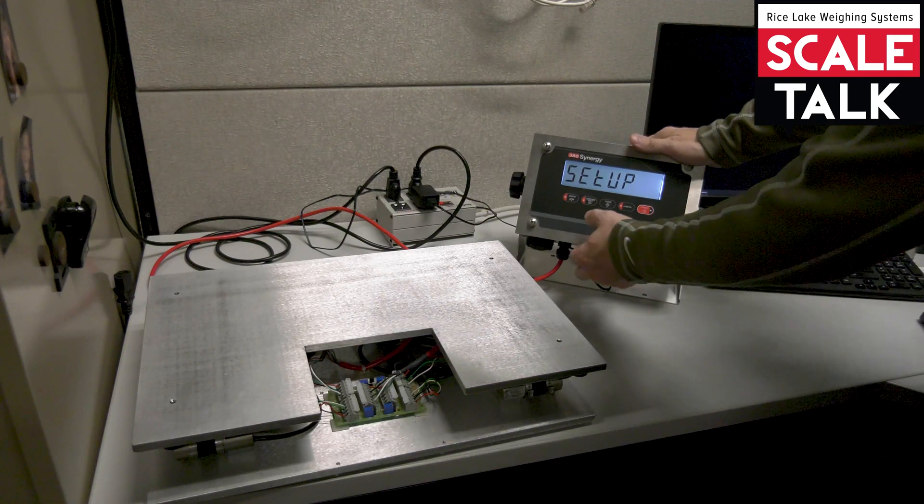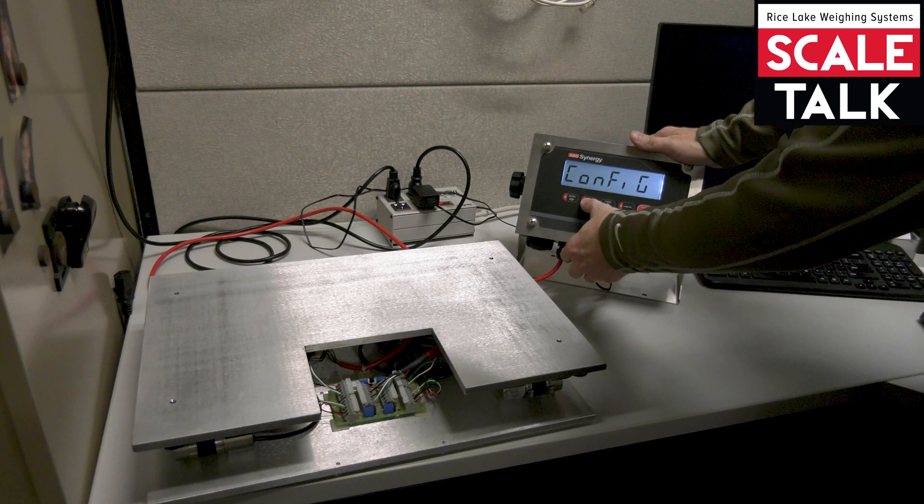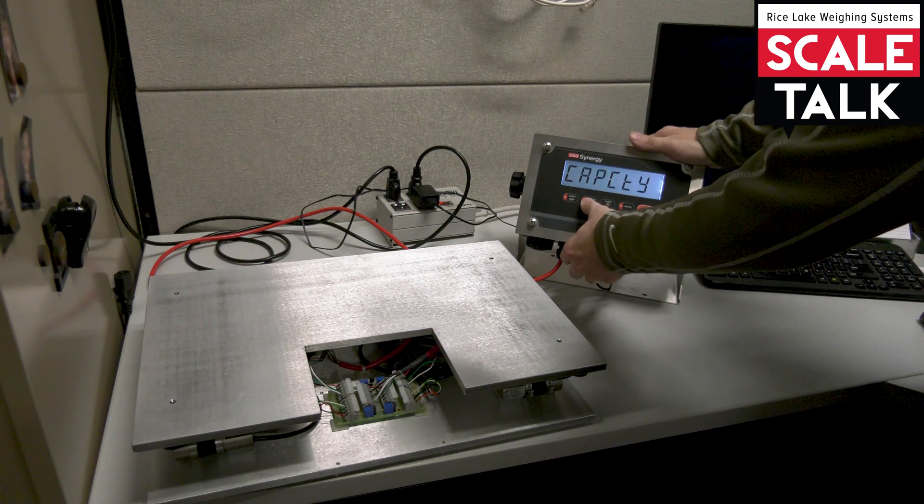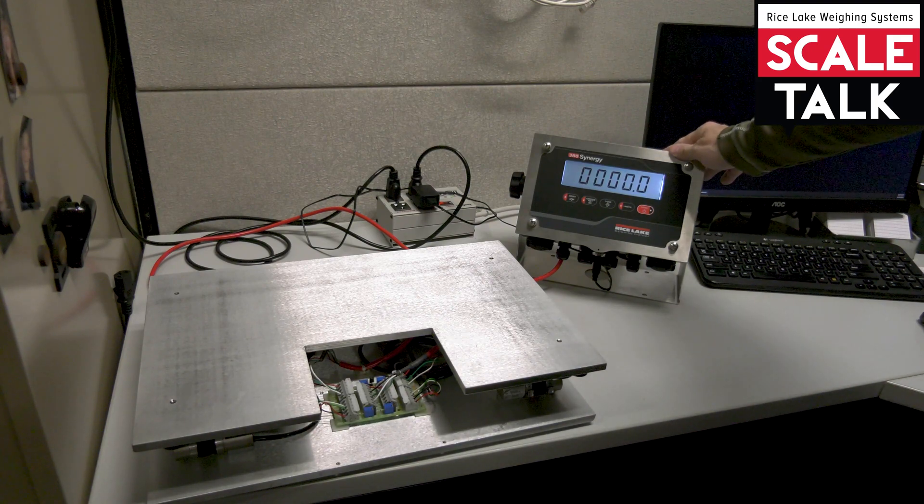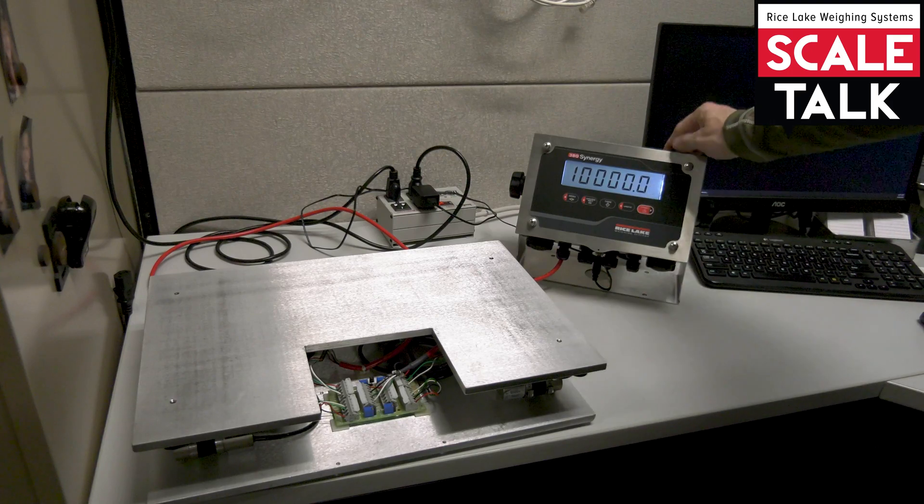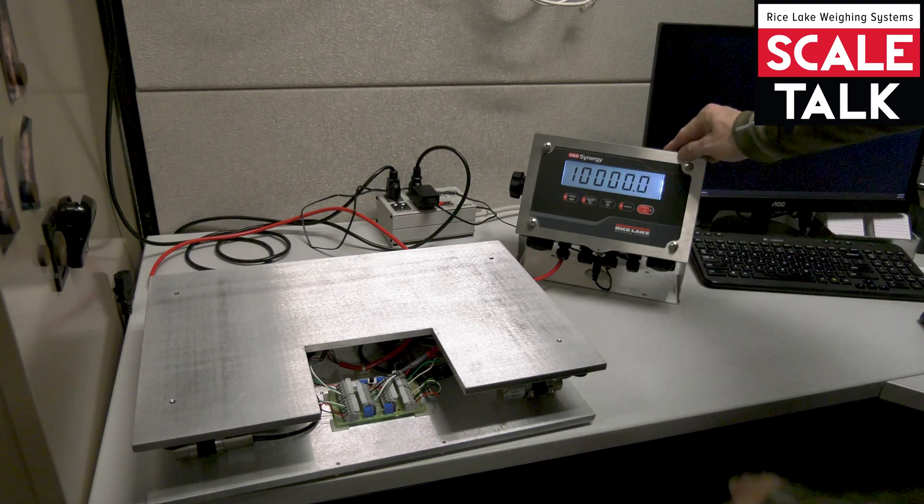From here I'm going to navigate down to config, down to capacity, and down a third time where I see the default value of 10,000. Remember we wanted to make this a 50 pound scale, so we're going to make the adjustment here for the capacity.